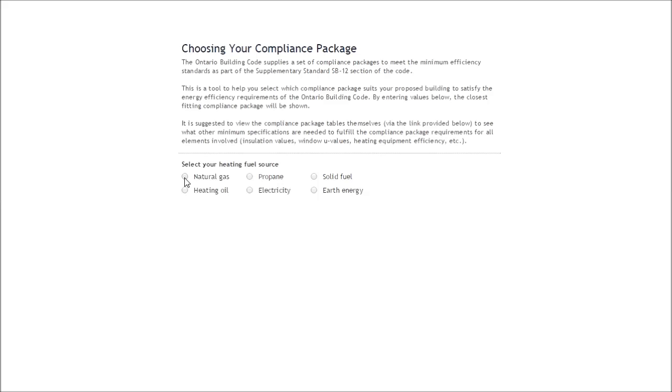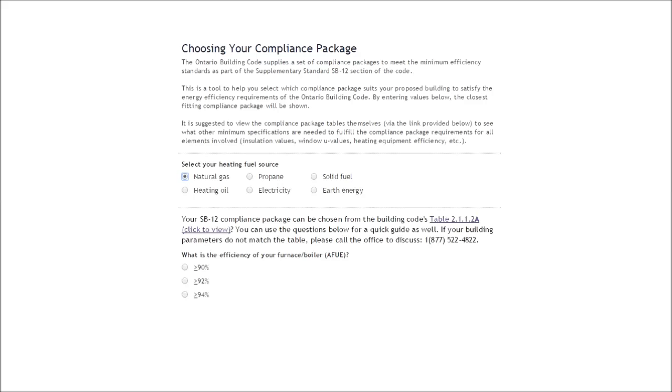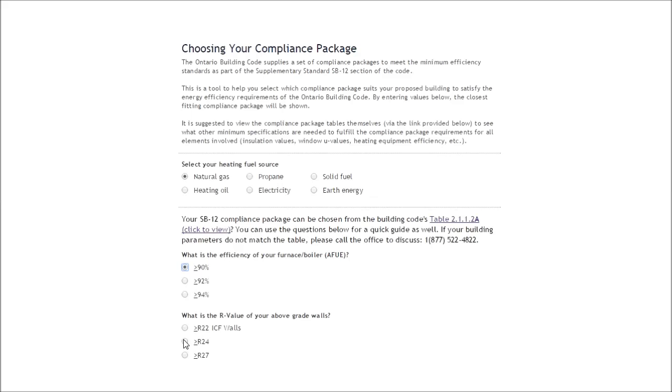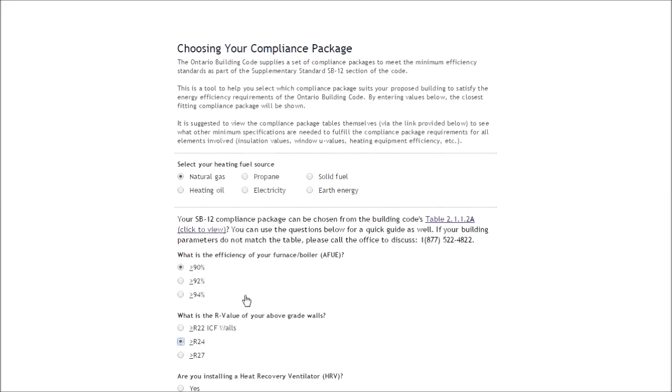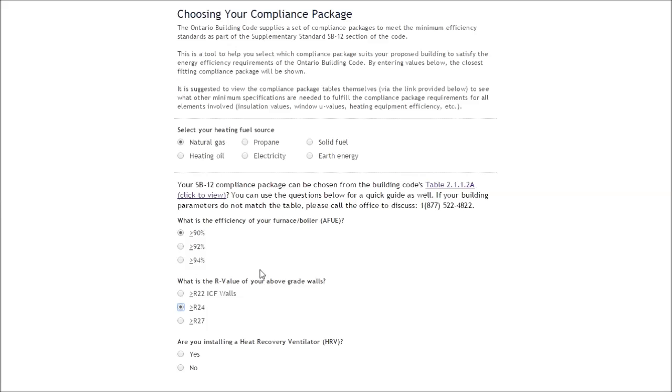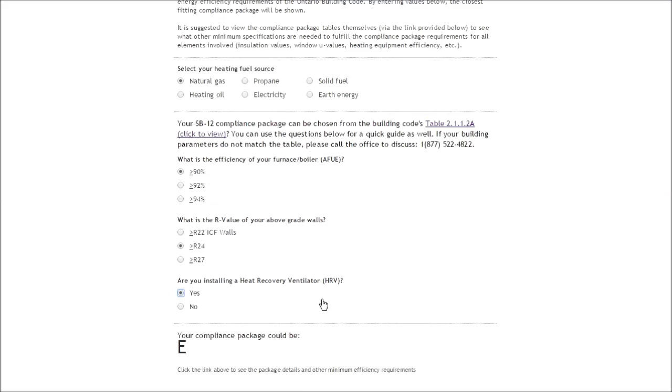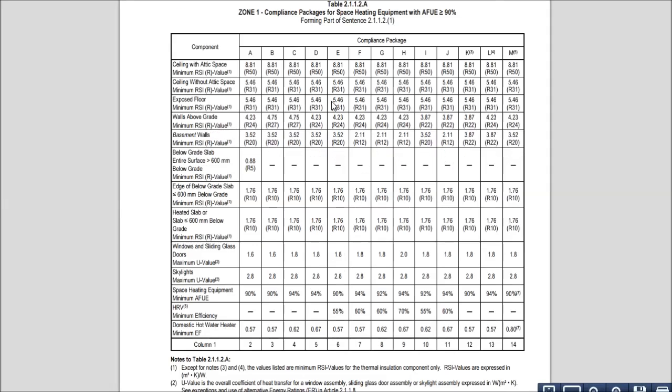For example, say you're using natural gas and it's a 90% efficient furnace and you have R24 in your above-grade walls and you are installing an HRV. That would be very close to compliance package E. There are other options that you could have, so to take a look you can see them here, but the vertical column here for E matches those values already.